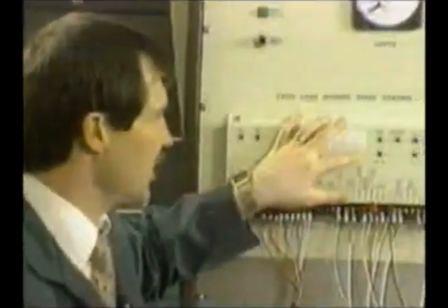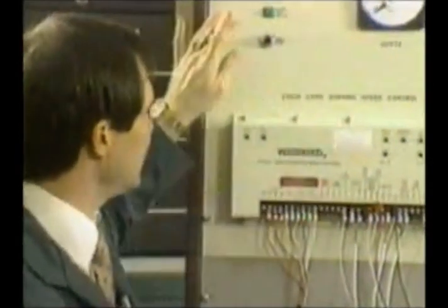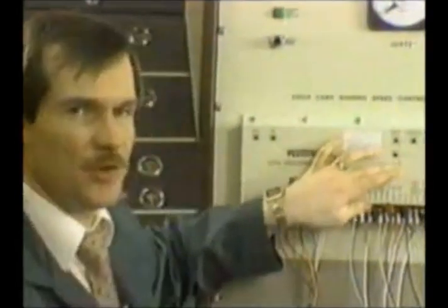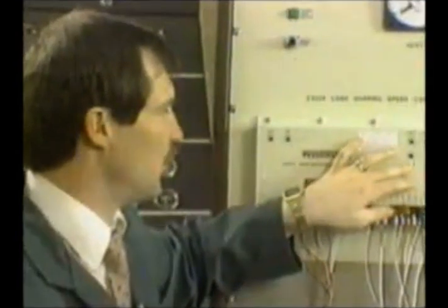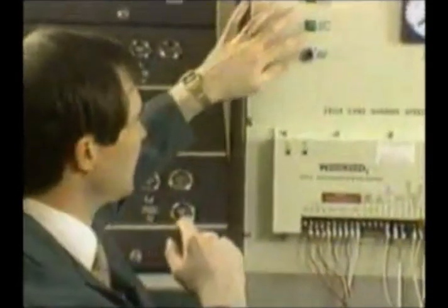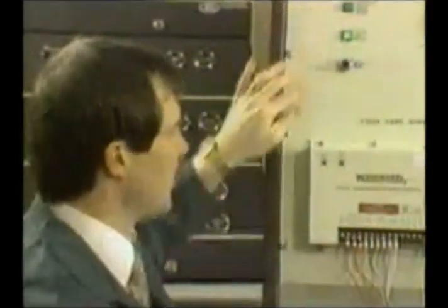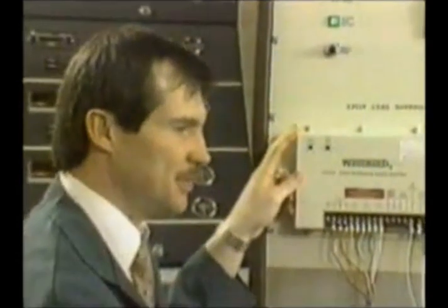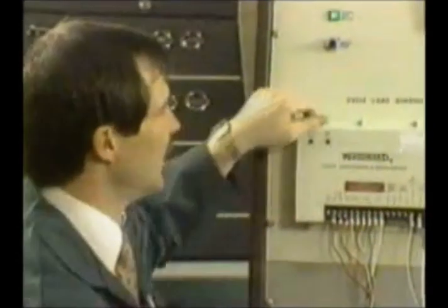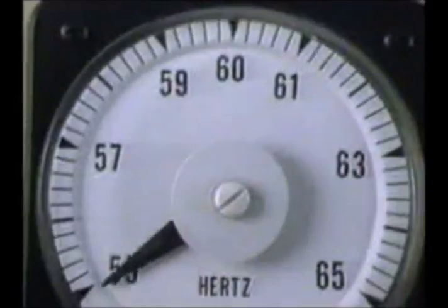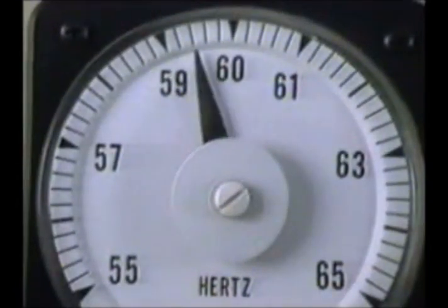So now, that shows you how I can set up my speed with the function generator. I need to talk about my ramp time. Once I hit this switch now, the ramp time is set for full or maximum ramp time, full clockwise. The control will linearly have a smooth acceleration from idle to rated speed. So if you watch the frequency meter, I close for rated. You can hear the speed in the background picking up slowly. If you watch your Hertz meter, we'll come right in and smoothly come into control at 60 Hertz.